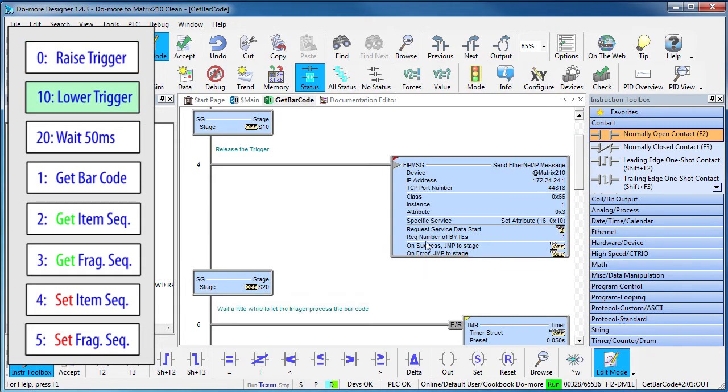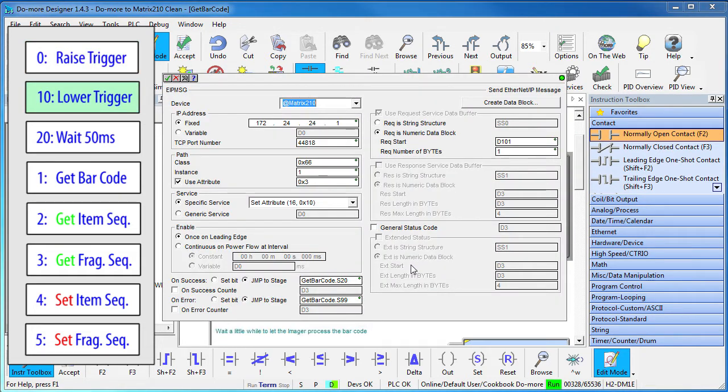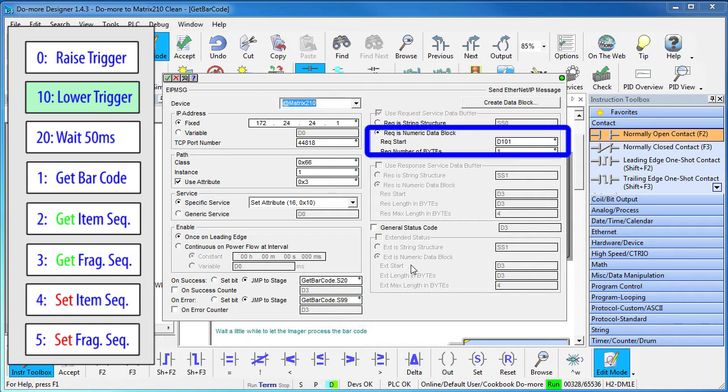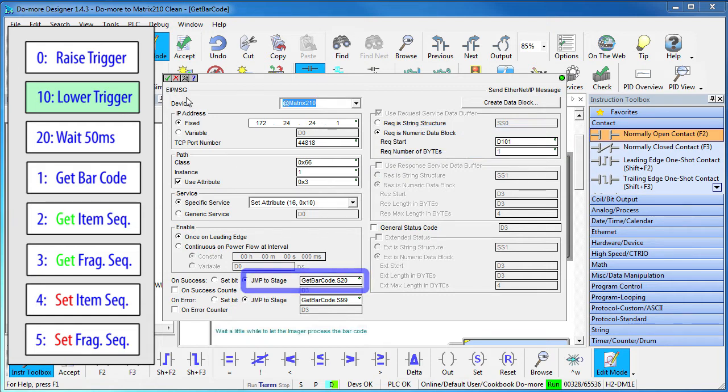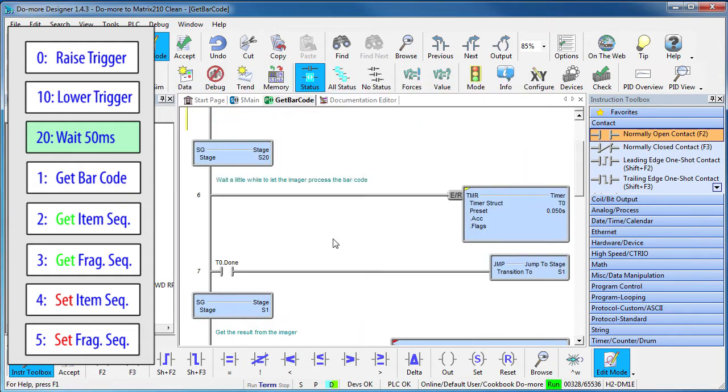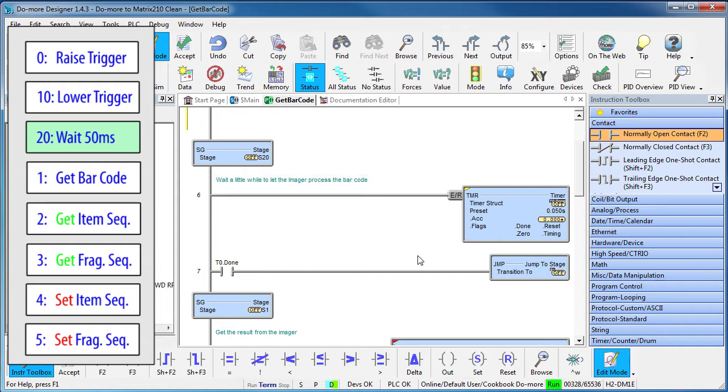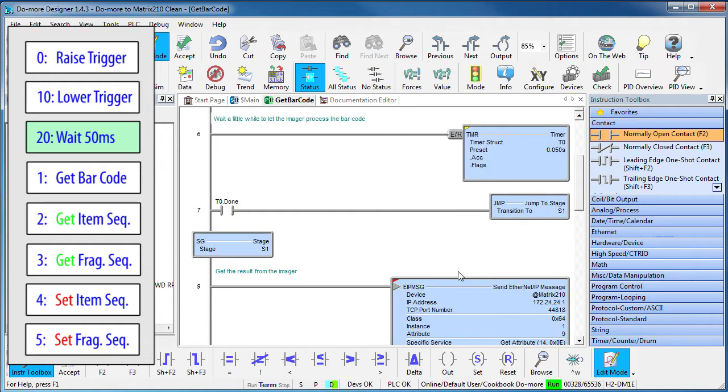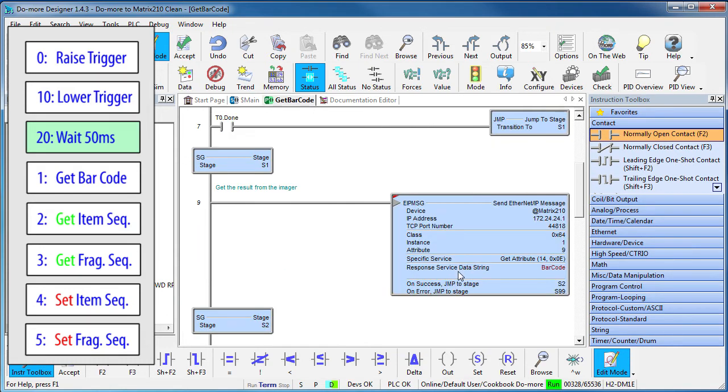Stage 10 releases the trigger so it's the exact same instruction except it sends this register which has a zero in it to clear the trigger bit and it jumps to stage 20 when it's done. In stage 20 we give the imager a little time to process the image. We start a timer and jump to stage 1 when the timer is done, which also shows that stages don't have to be in numerical order.